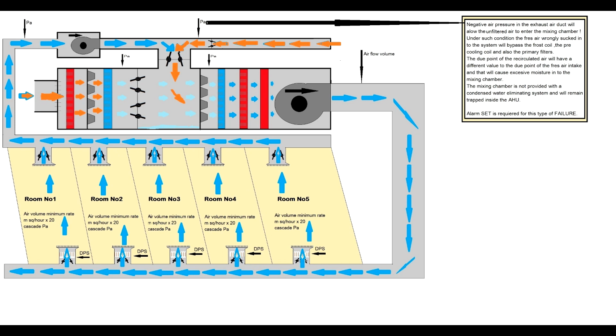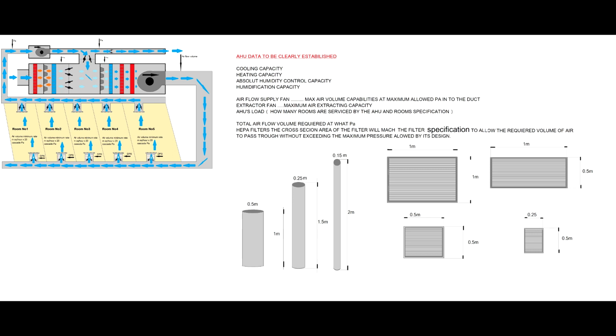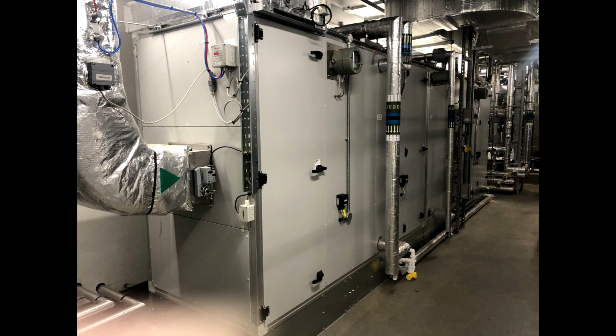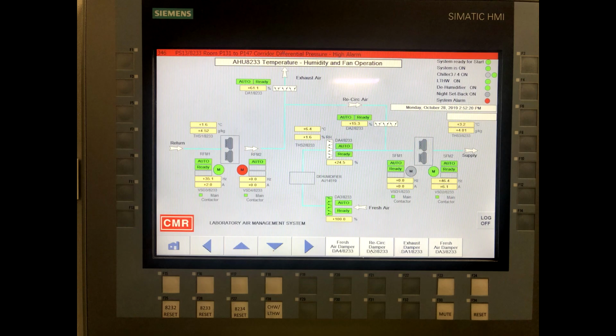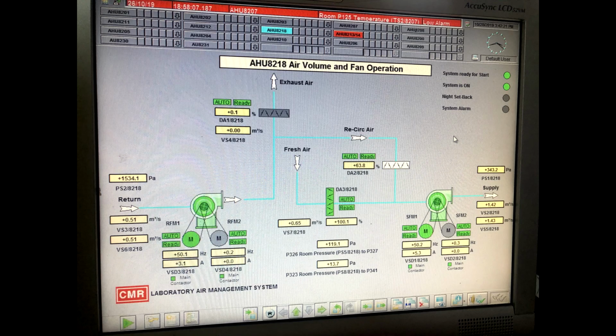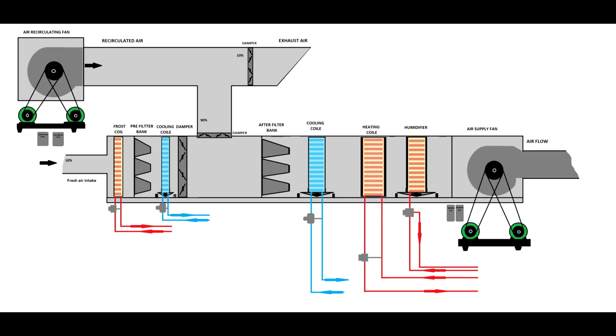And you look at that section, you will bypass the primary cooling coil, the frost coil, and the primary filter. On the right-hand side you see different cross-section areas for the filters. Even if some of them are small, they can push the same volume by increasing the pressure. But if you do not respect the HEPA filter maximum pressure allowed by the manufacturer, you will force more bacteria through that filter, and its efficiency will be nothing.